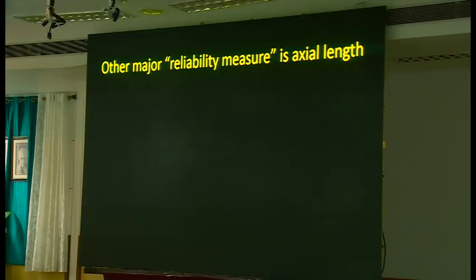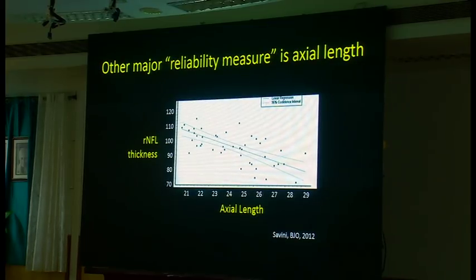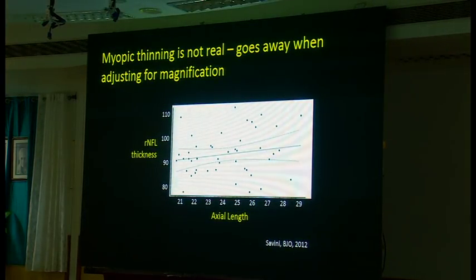We don't consider this a reliability factor but we really ought to, and that's axial length. This is a plot of retinal nerve fiber layer thickness against axial length, and you can see that as axial length becomes larger, RNFL thickness becomes thinner — in people with normal visual fields and no evidence of glaucoma. However, this is not really a true effect. If you adjust for the magnification effects that OCT applies, you don't see any relationship anymore. What appears as thinning with increasing myopia is really just a magnification artifact from the optics of the machine.